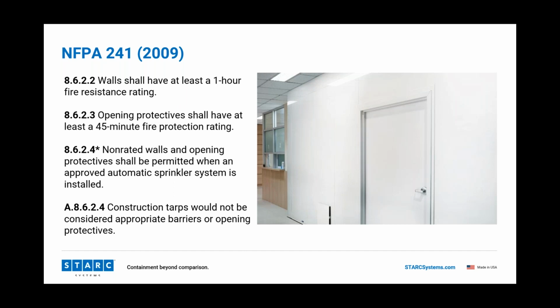So the reason for that is that construction tarps, not only from a fire protection perspective, don't meet the flame spread rating index or the smoke development index. They also are not appropriate ICRA barriers. So from an infection prevention side, very, very critical. I personally do not like construction tarps at all. Not a proponent.